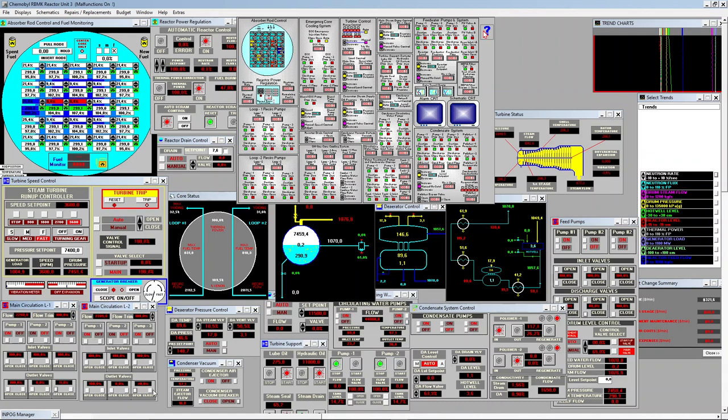And open the discharge valve. And you will see the voiding now decreasing to 20. You see the drum pressure increasing. You see the drum steam flow increasing. And the generated load, 1066, this will stabilize after everything goes flat, and I think it will stabilize around 1050.